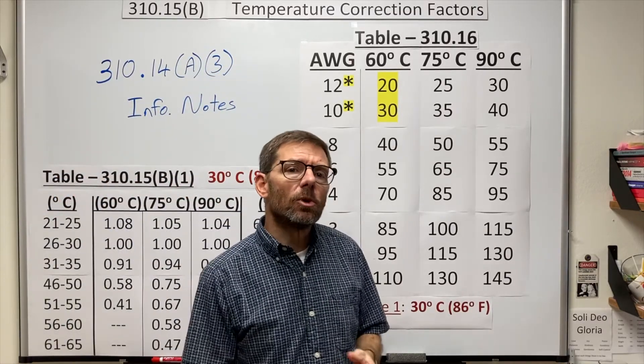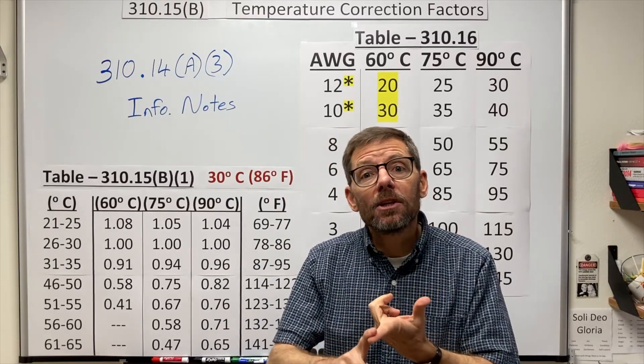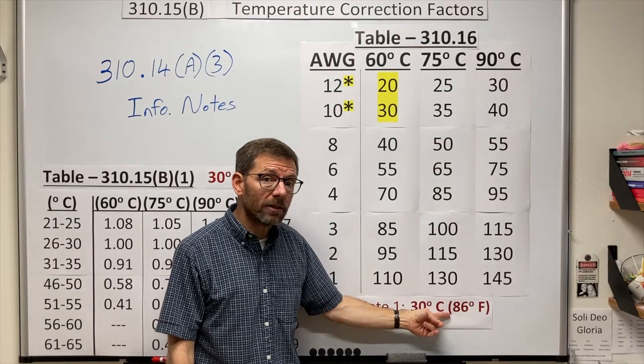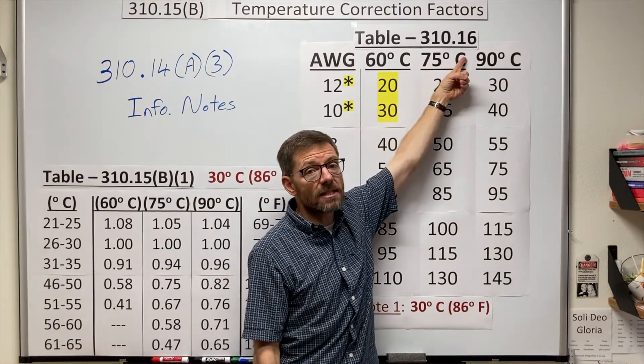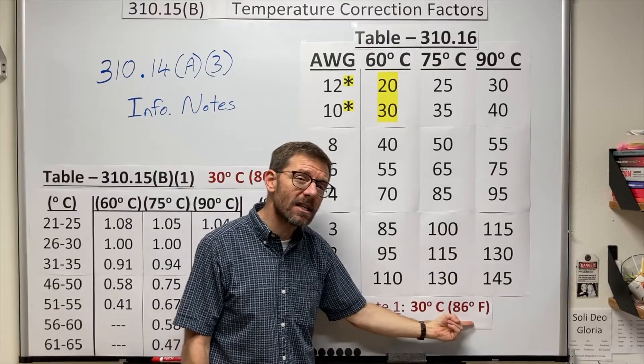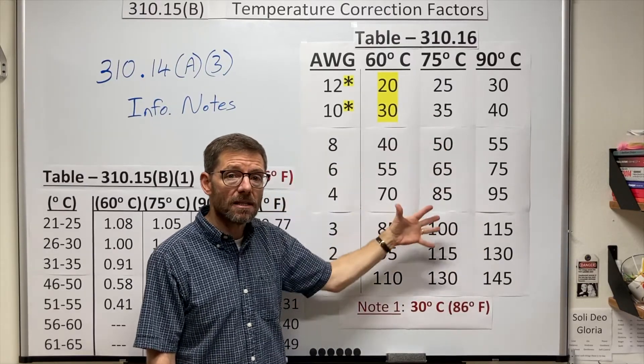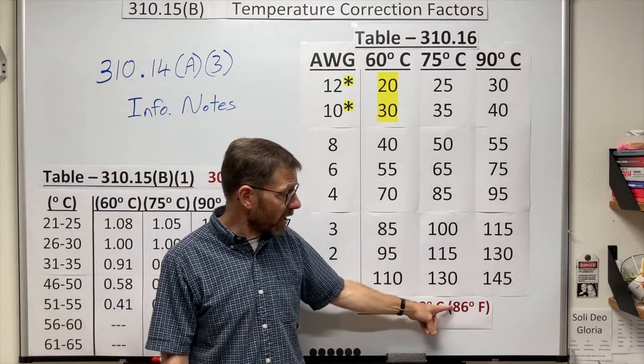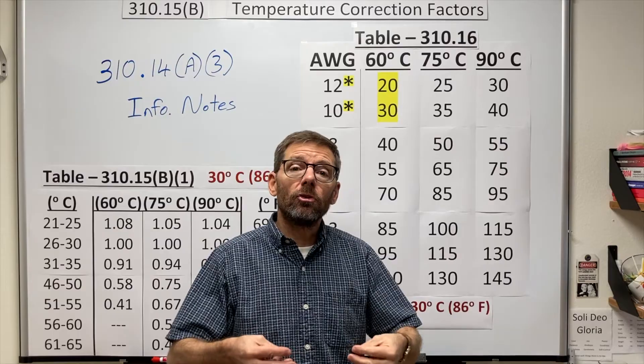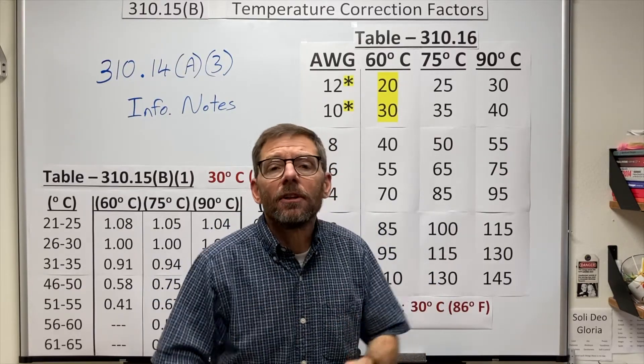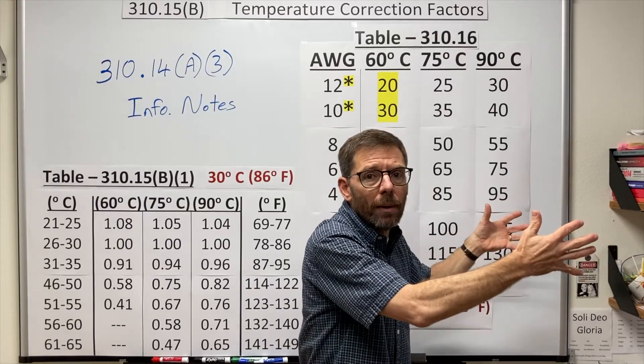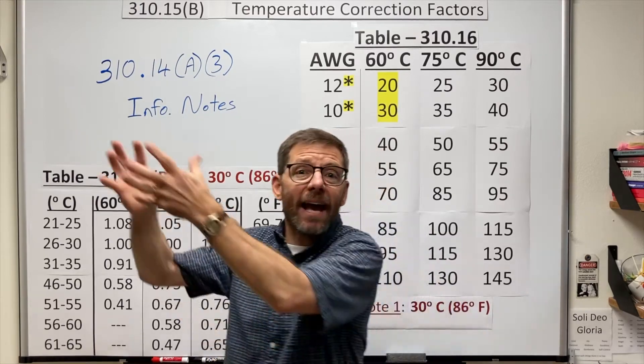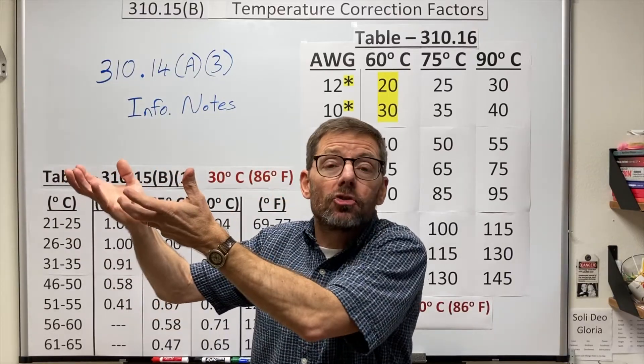So where am I going to worry about this at work? Well, outdoors or in non-air-conditioned buildings in parts of the country where temperatures are often hotter than the conditions required for your ampacity tables. Table 310.16 requires an ambient temperature of 86 degrees Fahrenheit for these ampacities. If you're hotter than that, you'll need to reduce the ampacities. But interestingly, if your environment is cooler than that, you may be able to increase the ampacities. Other locations might be industrial facilities with hot equipment, factory floors, or attics.